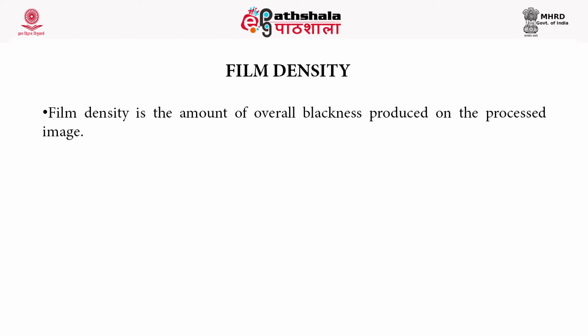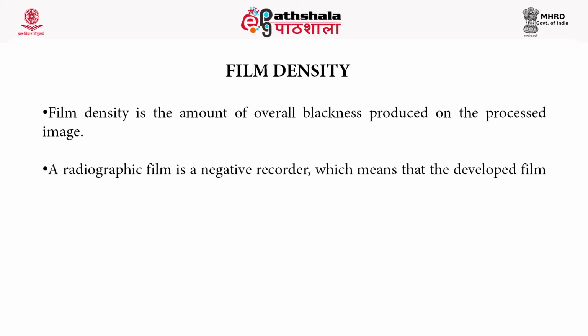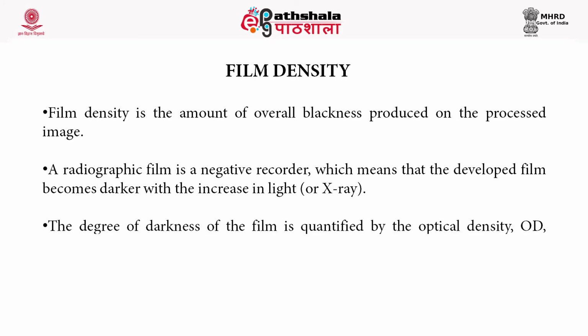A radiographic film, as has been mentioned, is a negative recorder, which means that the developed film becomes darker with the increase in light or X-ray. The degree of darkness of the film is quantified by the term optical density. It is written as OD and can be measured with a densitometer.